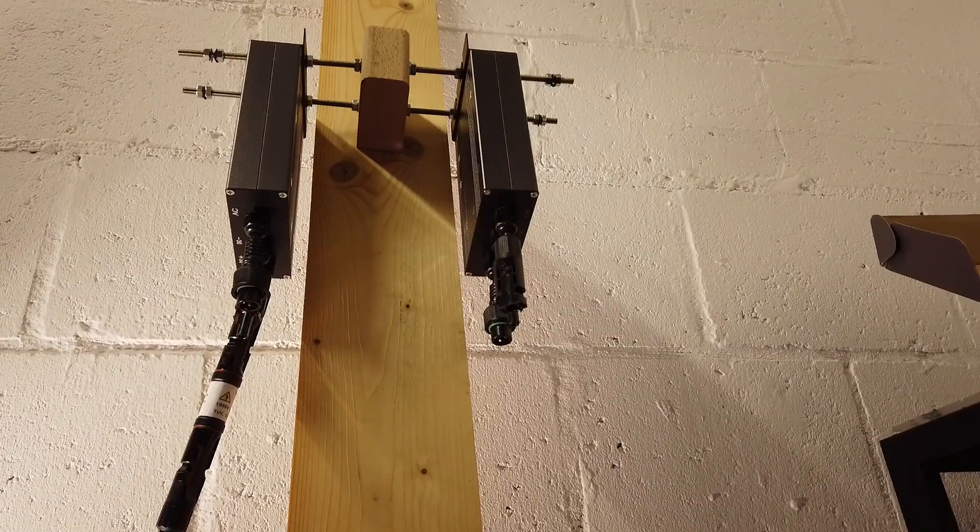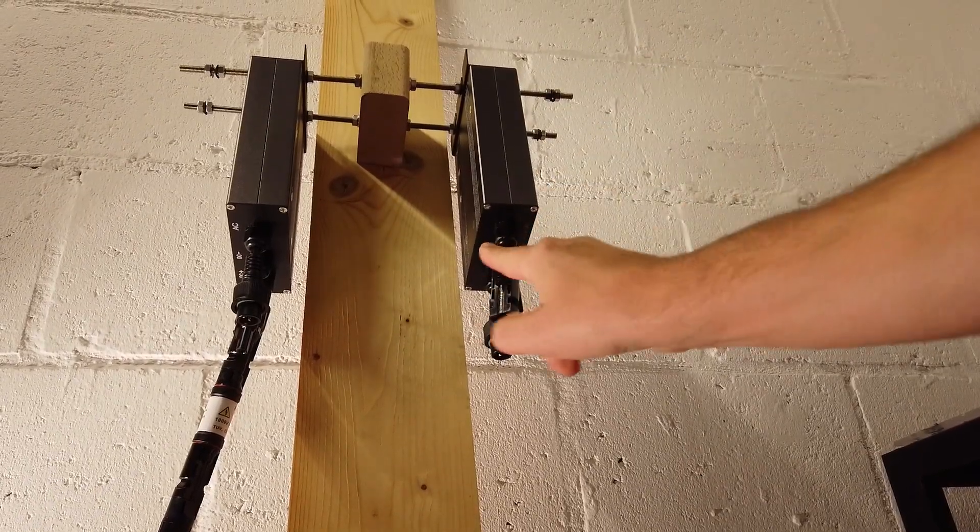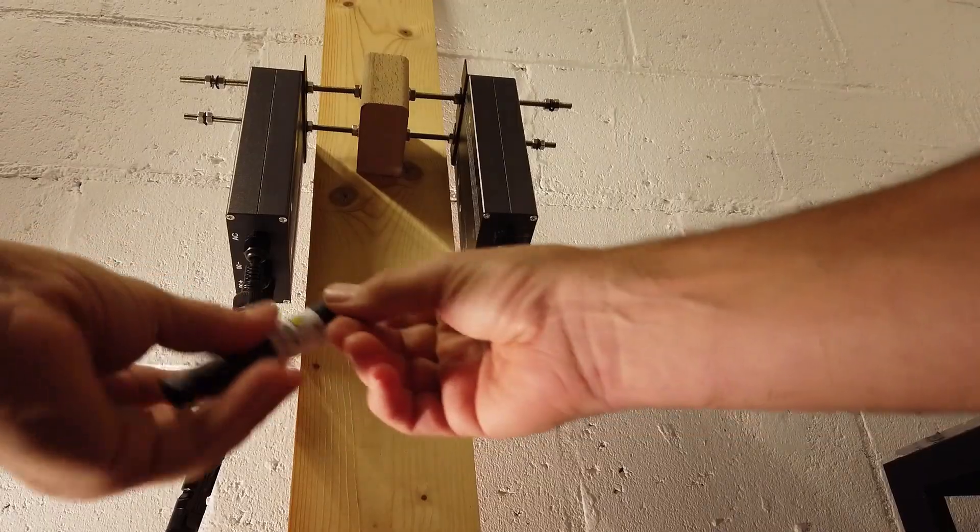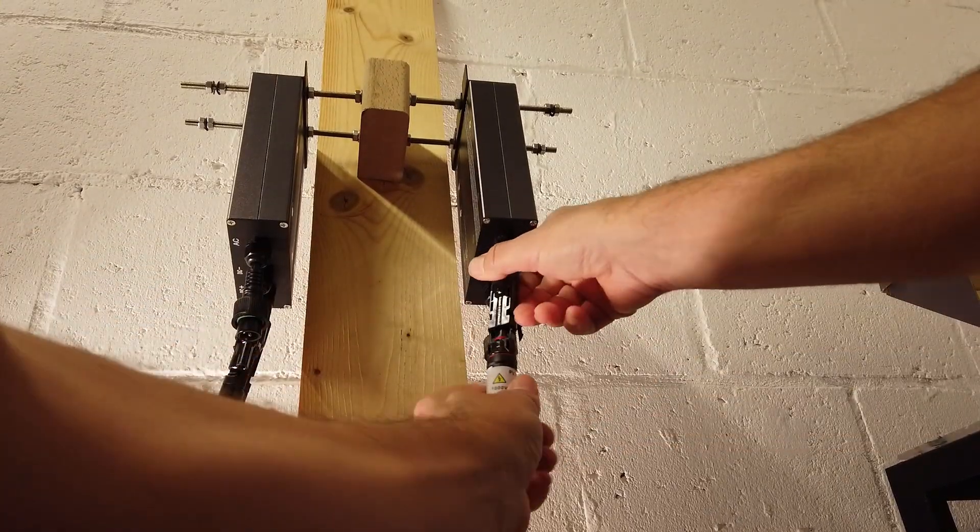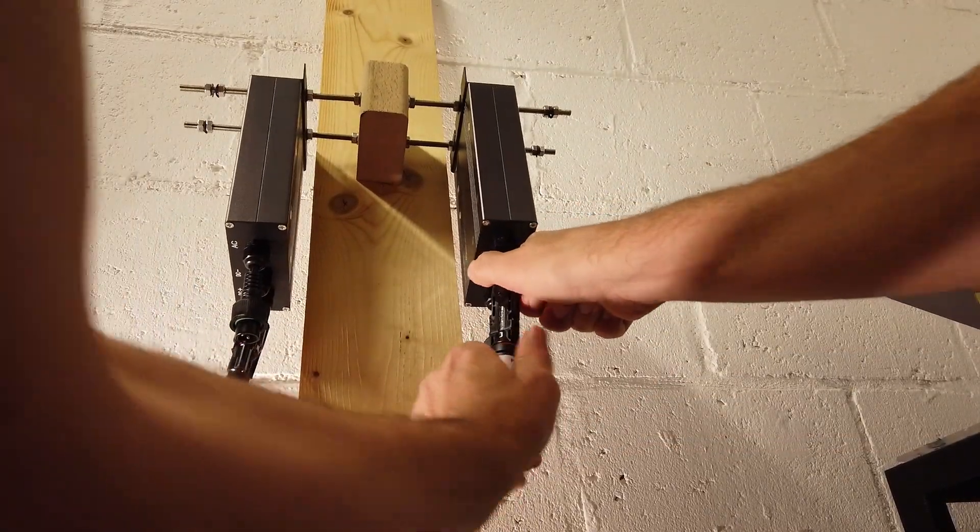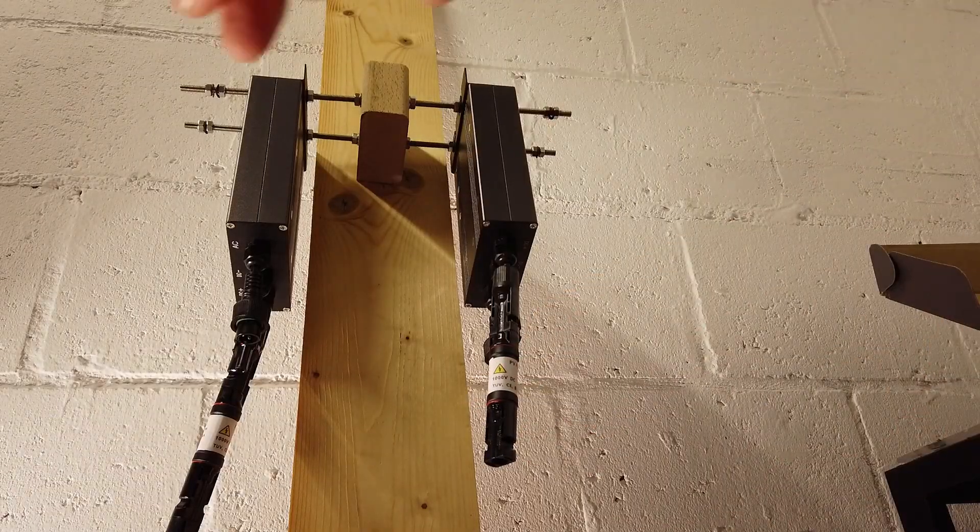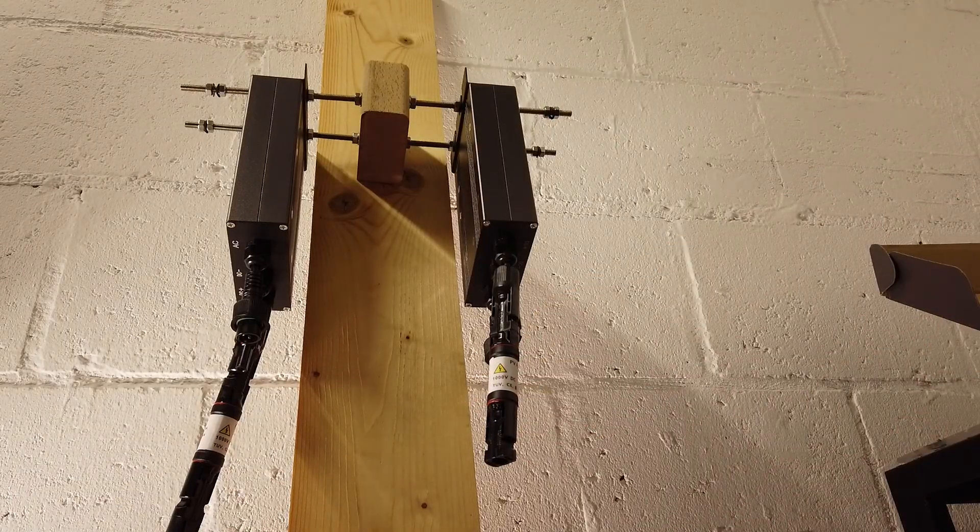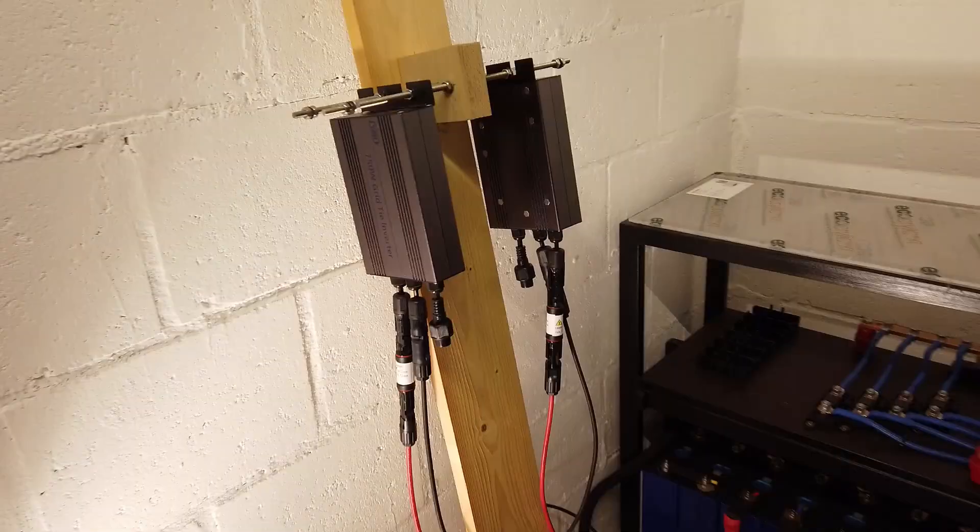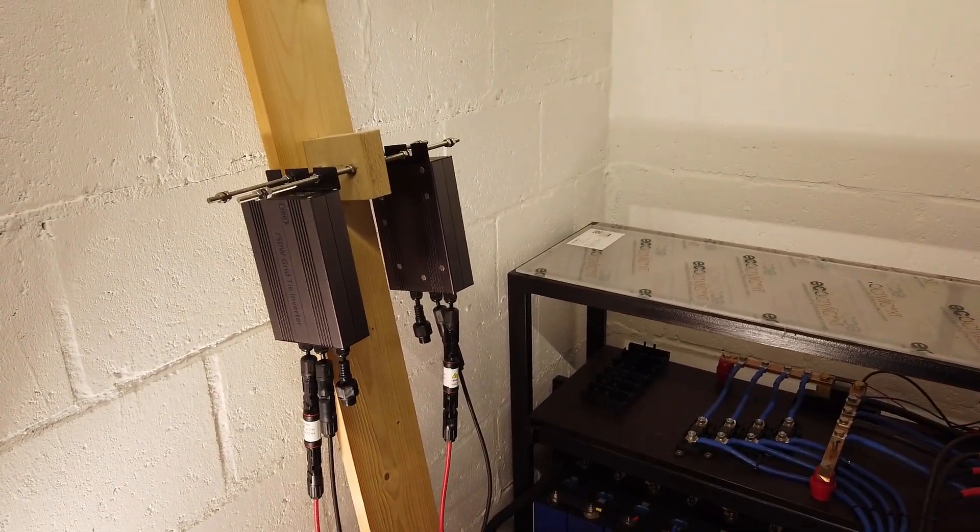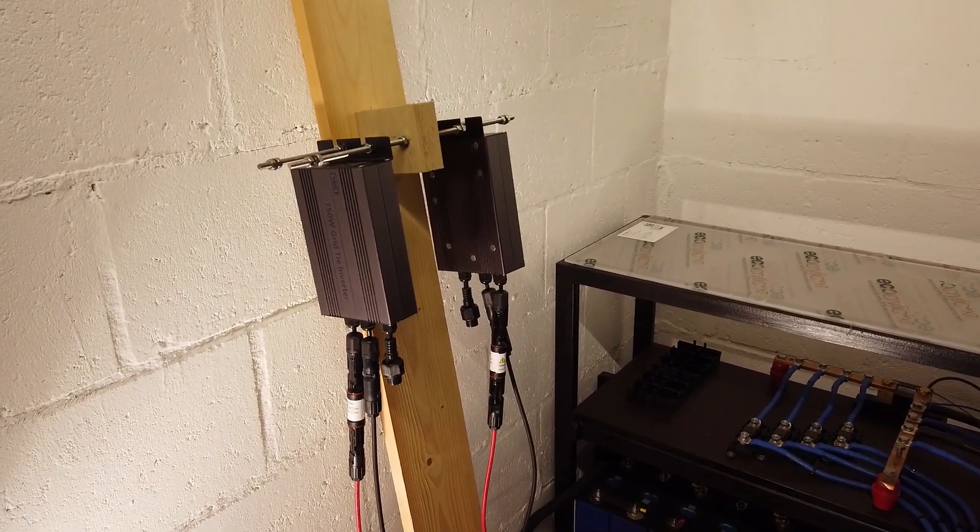Safety is a very important topic. I tried to add several layers of protection in each project. Here I'm installing an inline fuse on the positive pole of the microinverter. I installed a 15 amp model but you will see later in the clip that 20 amp was a better choice.